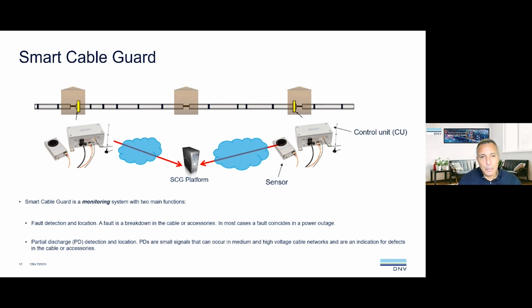The second aspect we measure is the development of partial discharge inside the cable. Partial discharge is a very good indicator for degradation of the cable and its isolation. This can detect weak spots and prevent faults, because by detecting these kinds of issues, you can start engaging in a condition-based maintenance approach.